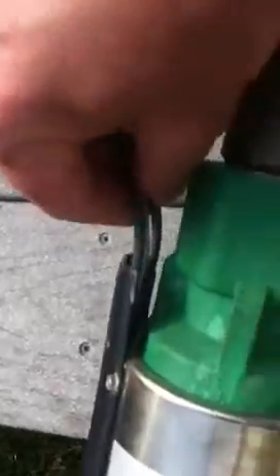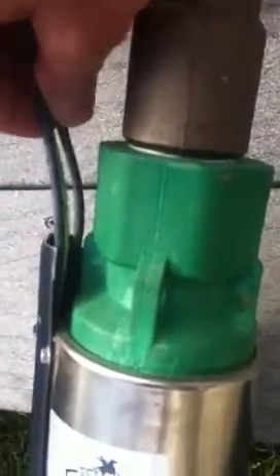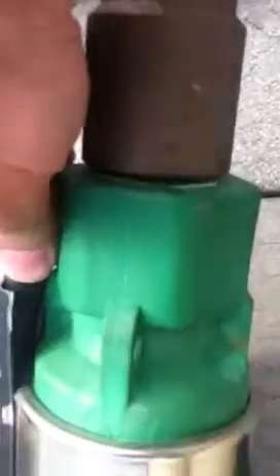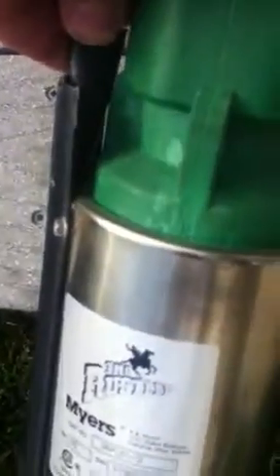So what we want to do is make sure that these pump leads, which are typically, as I've stated previously, of a much thinner insulation than the pump wire itself, or the pump wire that we install going up to the wellhead, we want to make sure, in this instance, that little protector slides up in there. You can see it going up in there right there, protecting that wire where it makes this bend across this stainless steel shoulder here that's on the pump head itself.